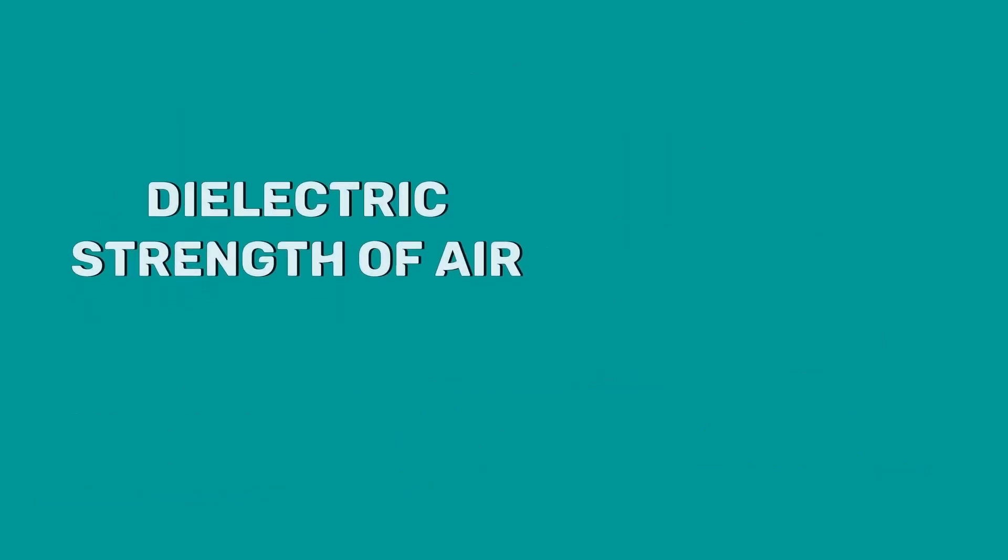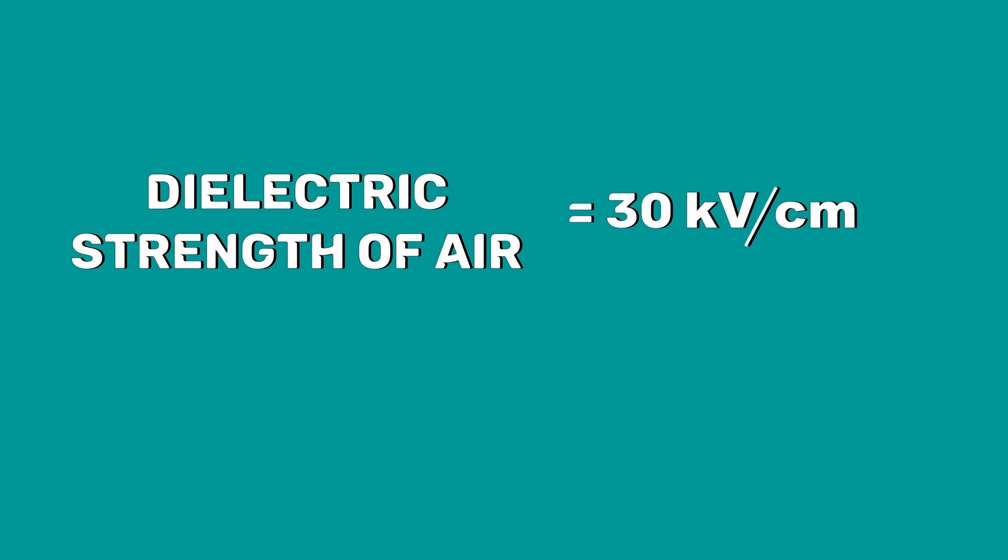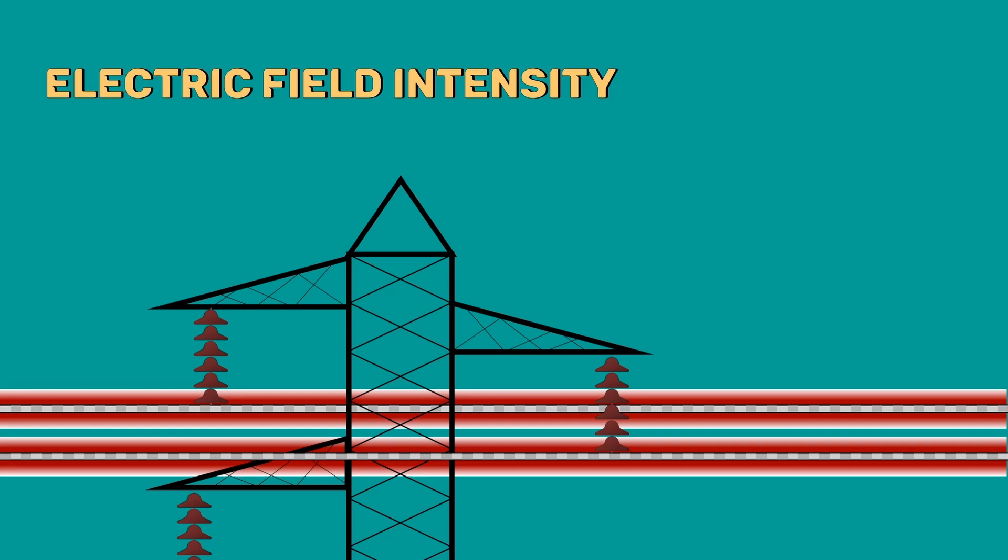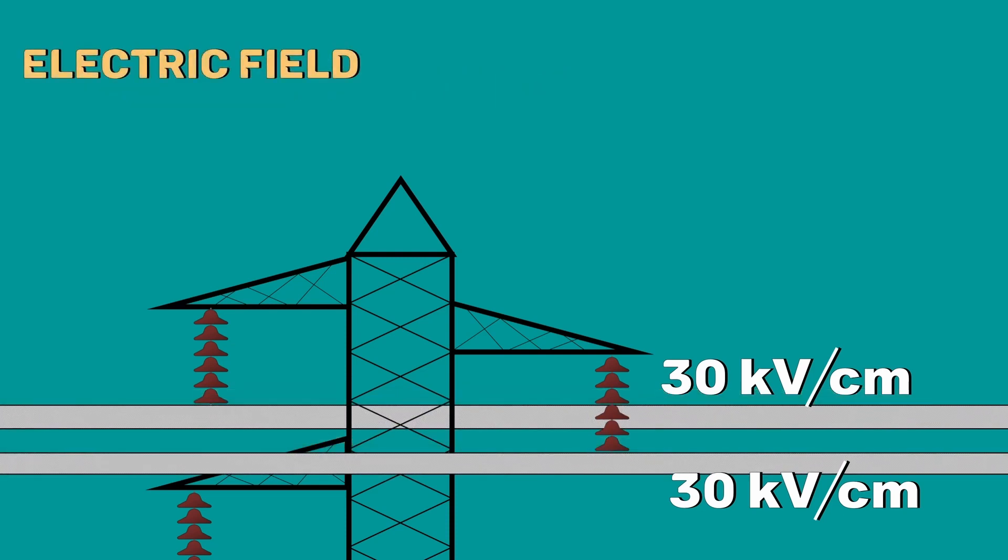The dielectric strength of air is 30 kV per centimeter. When the electric field intensity at the surface of the conductor reaches 30 kV per centimeter, the air around the conductor breaks down and acts as a conductor.